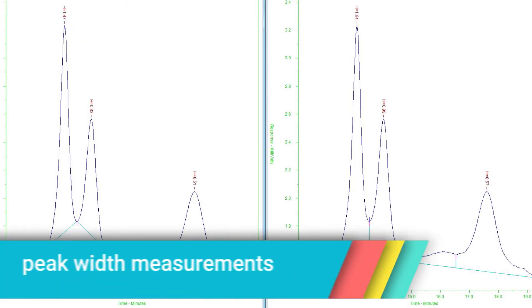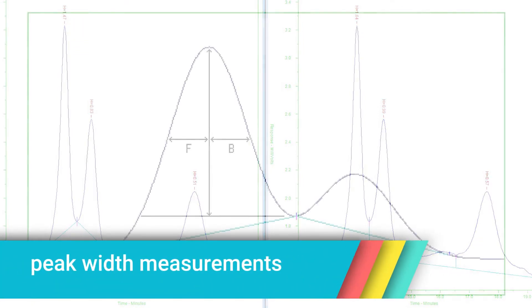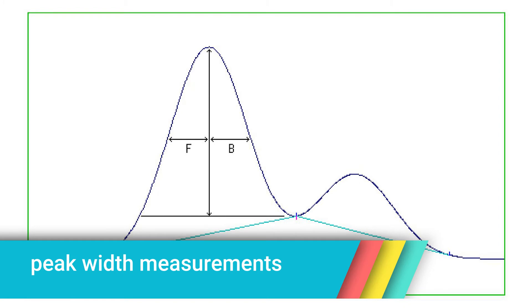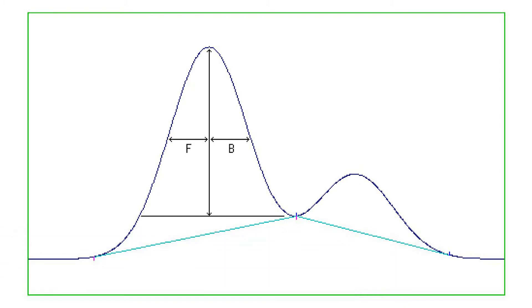Peak width measurements. The peak width is commonly defined as the full width of the peak measured at half height. The calculations are illustrated on screen now. ChromPerfect always measures peak widths using horizontal lines, even when the baseline is sloped.